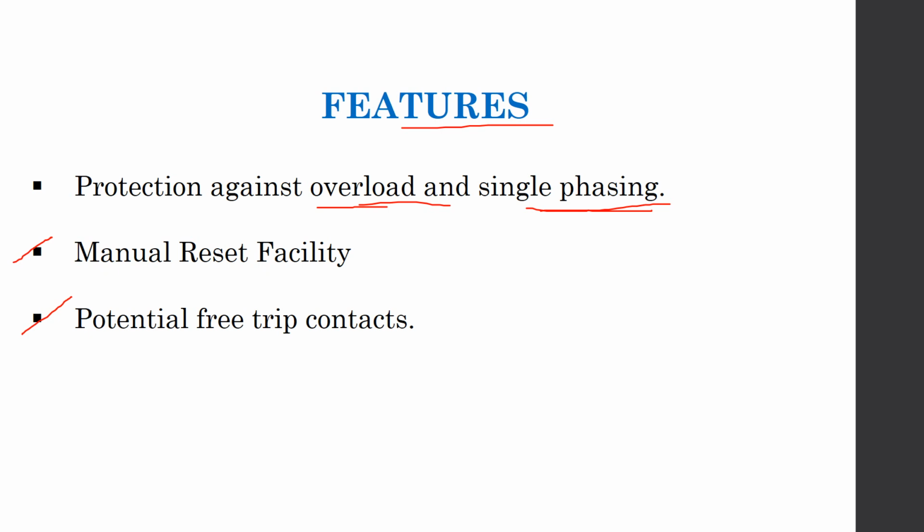Overload is a situation when a machine is loaded beyond its rated capacity. And whenever a machine is loaded beyond its rated capacity, it starts drawing an excessive amount of power from the electrical supply, which leads to the problem of overcurrent. This overcurrent can lead to excessive heating, and therefore the bimetallic strip can change its shape. Also, there is a possibility of winding insulation failure due to the overcurrent occurring as a result of overloading.